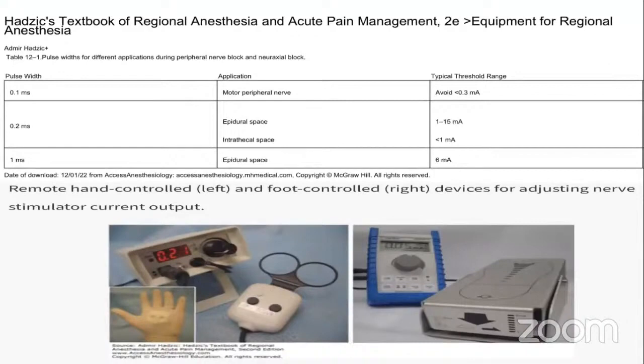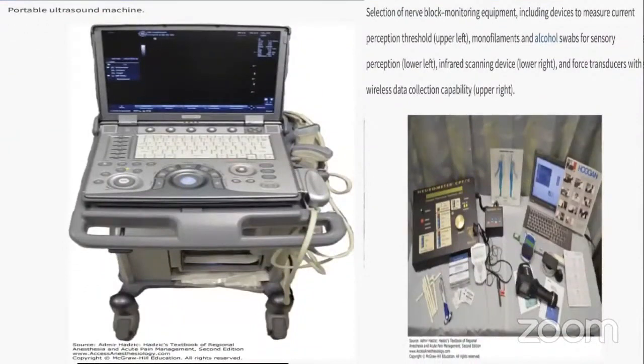So this is the pulse width for various applications during peripheral nerve blocks. Most likely the pulse width which is used for motor peripheral nerve block is 0.1 milliseconds with a threshold range. You need to avoid less than 0.3, right? And these are other types of nerve locators which are used for adjusting the nerve output. There are various ones which are available. Now this is a portable ultrasound machine. One must remember that selection of nerve block monitoring equipment, including devices to measure the current perception threshold, monofilaments and alcohol swabs for sensory perception, infrared scanning device and force transducers with wireless data collection capability, is what is recommended for a safe technique. So now I am coming to the end of my presentation.